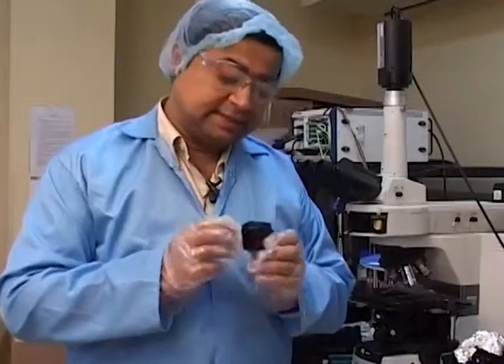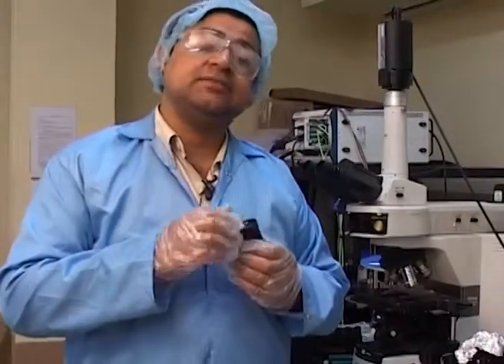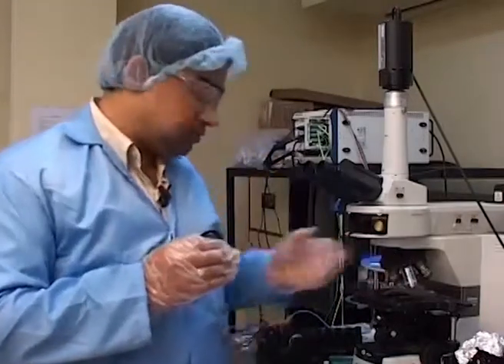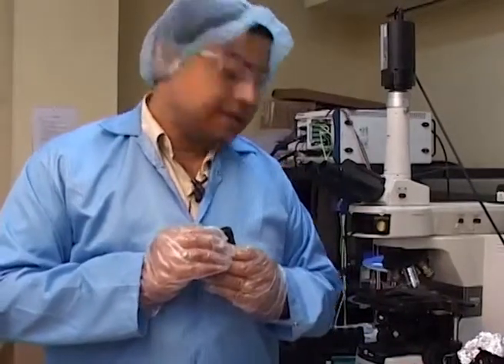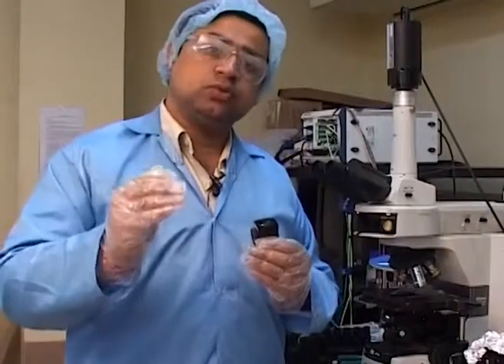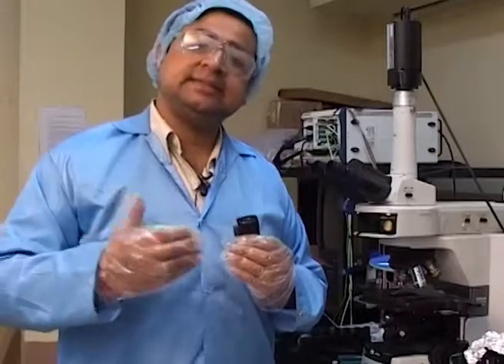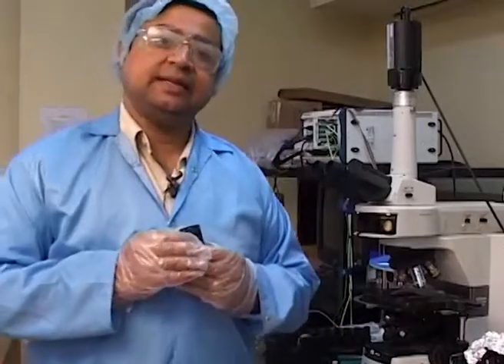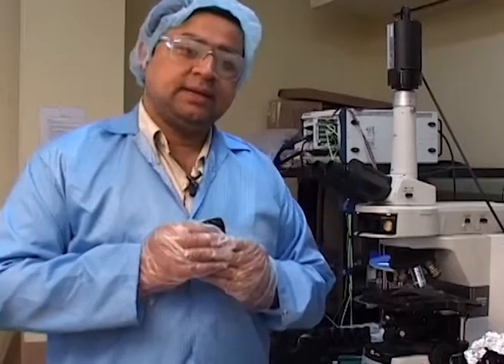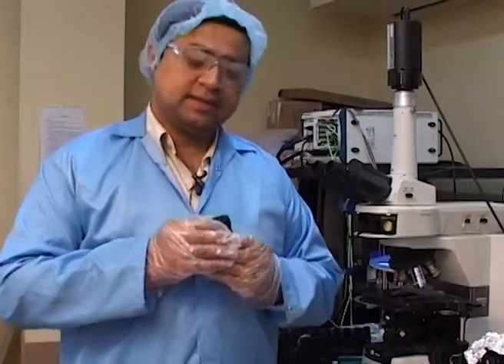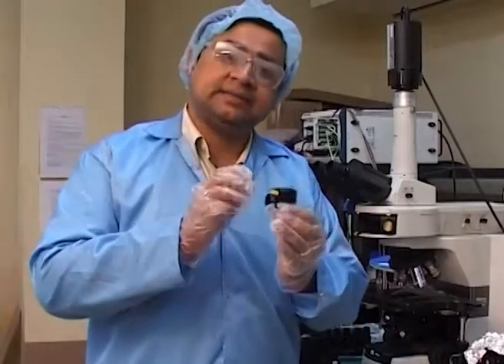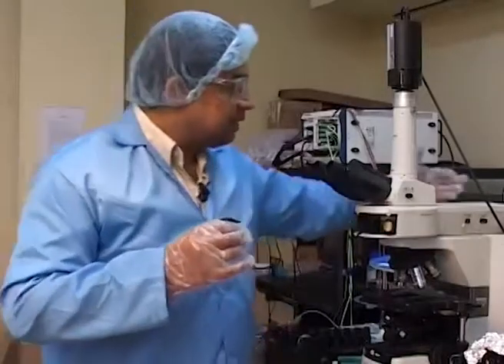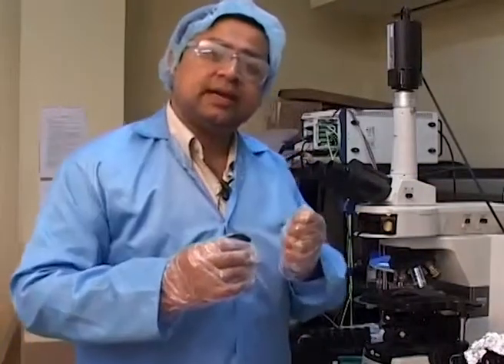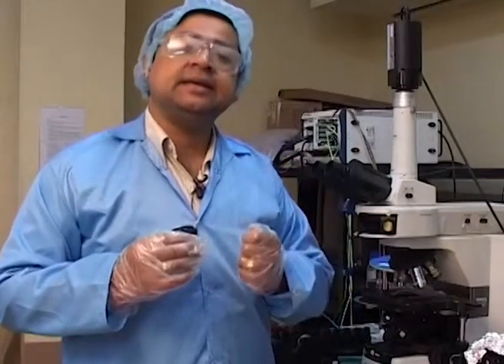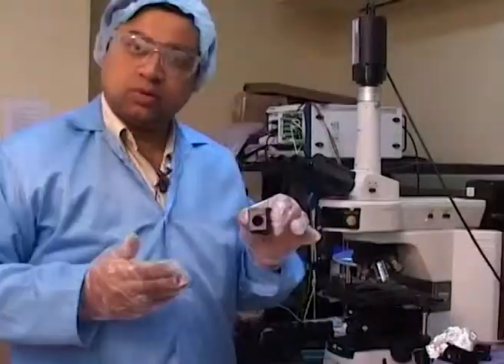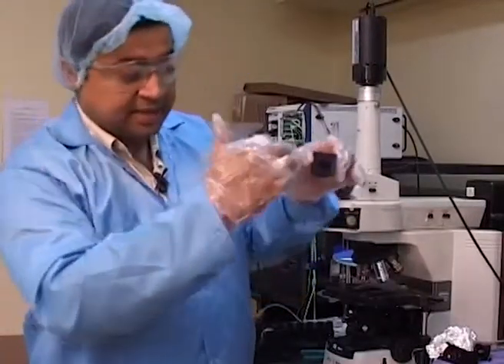The purpose of this filter is essentially to take off the unnecessary frequencies from the UV. As I told you, this microscope also has the capability of doing fluorescence measurements. It is almost always important to be able to excite a certain dye with a certain wavelength of light. Let's say we have a dye which is excitable in the range of 390 nanometers wavelength. So I should have some cutoff mechanism where all the different components of the UV coming from the illumination source to this filter get cut off except the 390 plus minus maybe about 20 nanometers.